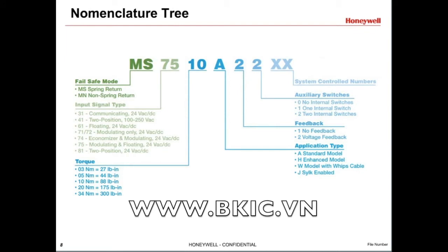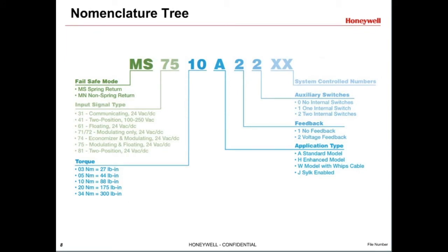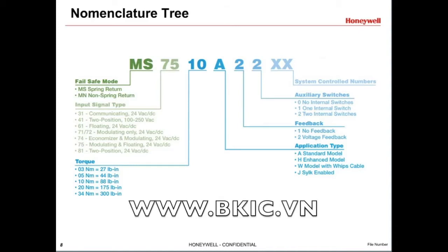Here's a more detailed nomenclature tree with an example. As you can see, part numbers for DCAs are defined by certain characteristics. For example, let's look at the MS7510A2206. The S indicates it is a spring return actuator, and there would be a different letter for a non-spring return fail-in-place actuator. The 75 means it has the capability to accept either a modulating or floating control signal. And the 10 means it has 10 Newton meters, or 88 inch-pounds of torque.